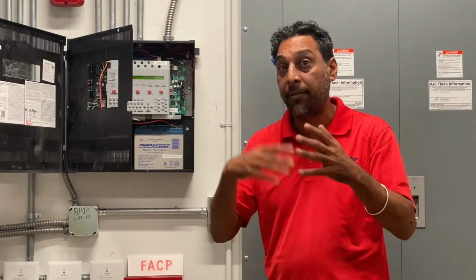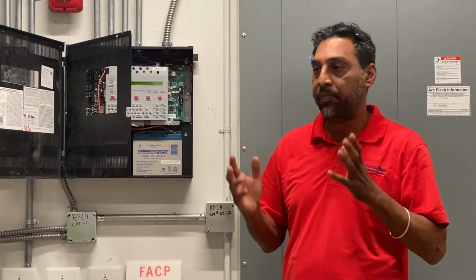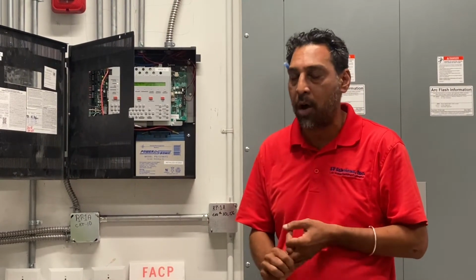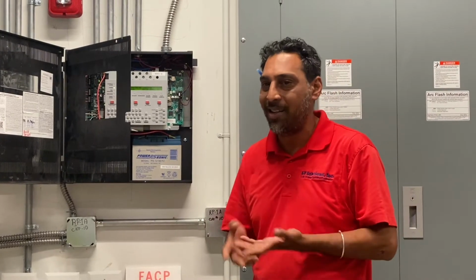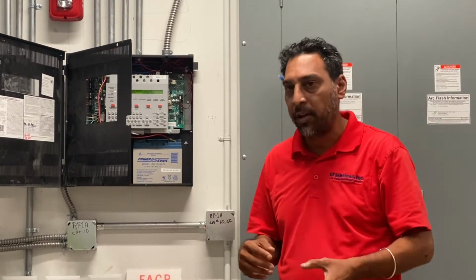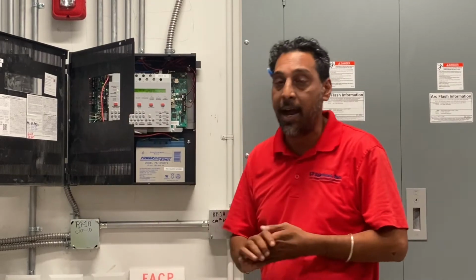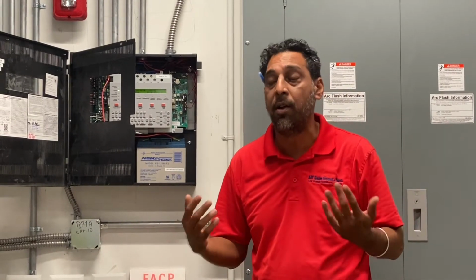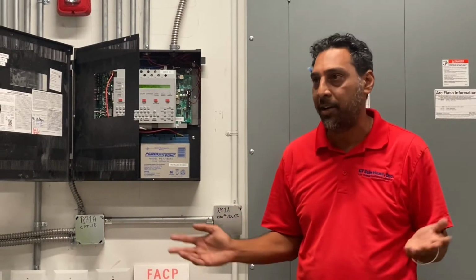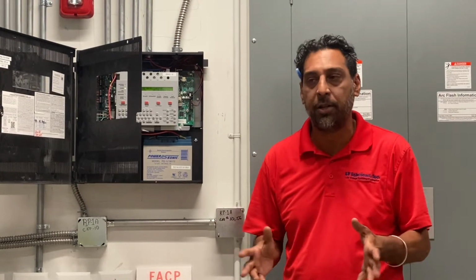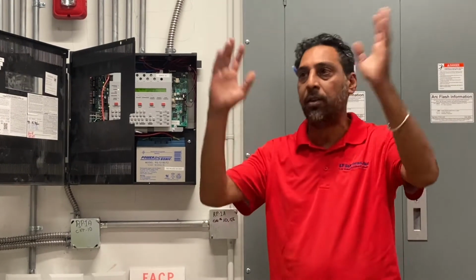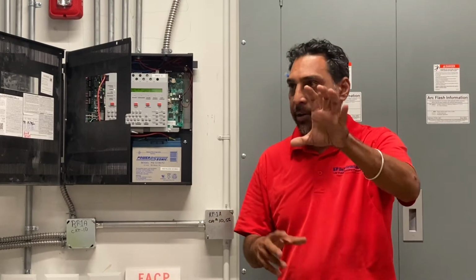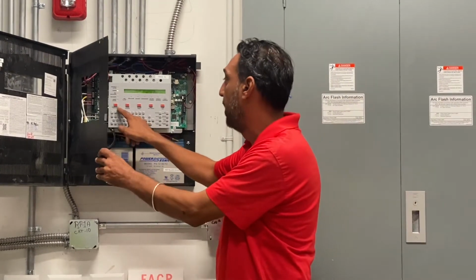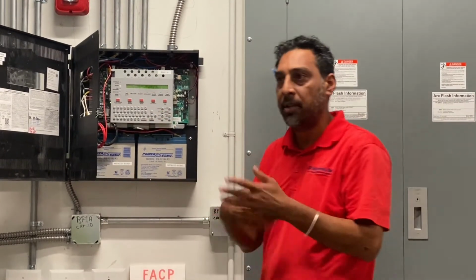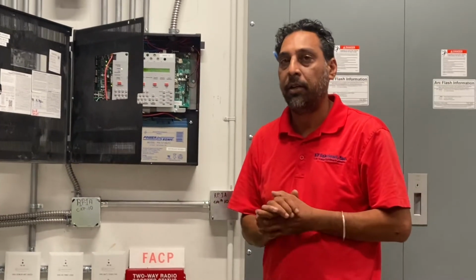And I will do a live test with you guys here shortly. Pull stations, smoke detectors, water flows. Now your water flows are what we call non-silenceable. So once the water flow flows, you can hit here and hit signal silence, but the water flow is not going to silence. By code, they don't want it to be silenced. I don't agree with it, because if you're in a full-fledged fire here, or they're running and trying to shut stuff off, but that's how this jurisdiction works. So basically, once they fill the water back up and their switch clears, then you just hit acknowledge, system reset. Once that water flow is clear, then you're good to go.